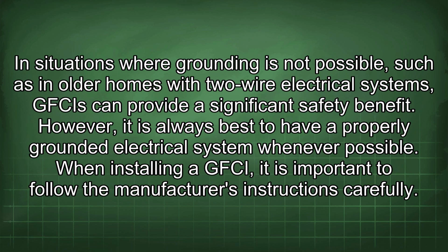In situations where grounding is not possible, such as in older homes with two-wire electrical systems, GFCIs can provide a significant safety benefit. However, it is always best to have a properly grounded electrical system whenever possible. When installing a GFCI, it is important to follow the manufacturer's instructions carefully.